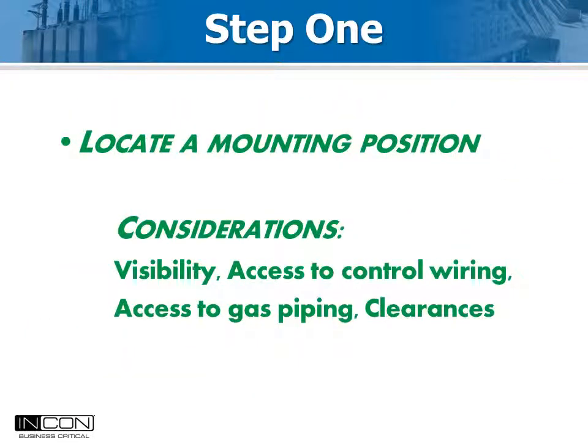Begin by looking at the control cabinet. Look for a space that is easy to get to, easy to neatly run wires to, and close to the terminal block that terminates the bushing CT circuits. Preferably, the Optimizer 2 should be powered by station battery voltage, so that wiring should be accessible also. Some like to see the display through the cabinet window. This is often possible, but check to be sure there is clearance so the cabinet door will close before you drill.